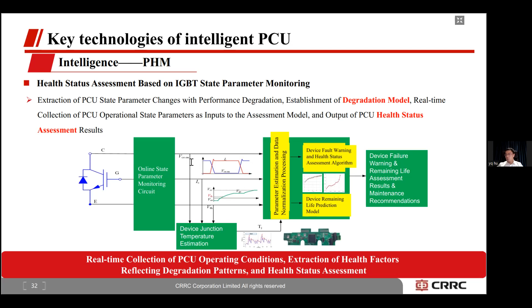We also applied our advanced PHM technologies in this device, including online state parameter monitoring circuit, device junction temperature estimation, parameter estimation and data normalization processing, device fault warning and health status assessment algorithms, device remaining life prediction model, device failure warning and remaining life assessment results, and maintenance recommendations. With these PHM technologies, we can collect real-time PCU operating conditions, extract health factors reflecting degradation patterns, as well as conduct health status assessment.